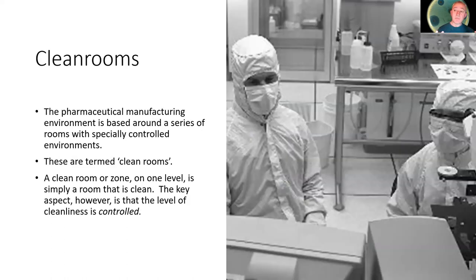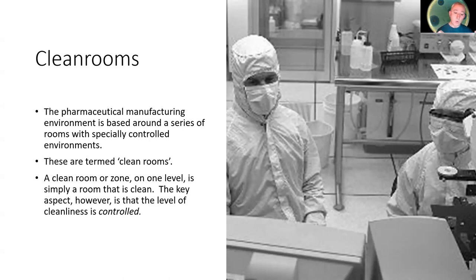Clean rooms are essential for the manufacture of pharmaceuticals — these are rooms subject to specially controlled environments. We determine the cleanliness of a clean room by measuring the concentration of airborne particles within a given volume, typically one cubic meter of air. We don't know whether those particles are inert or whether they are carrying microorganisms. Very few microorganisms are free floating within clean rooms; most are attached to other particles, often rafts of skin matter. So it's very important that we achieve a cleanliness class and then control this level of cleanliness.